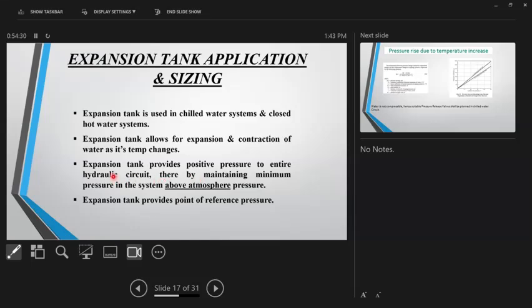But for timing, just read and try to grasp this. The expansion tank provides positive pressure to the entire hydraulic circuit, thereby maintaining minimum pressure in the system above atmospheric pressure. We will see what this means. And the expansion tank provides a point of reference pressure. This also we'll see what it means. So the expansion tank is required for expansion and contraction of water. It also ensures positive pressure in the system at all points, and it also provides what is known as a reference pressure.